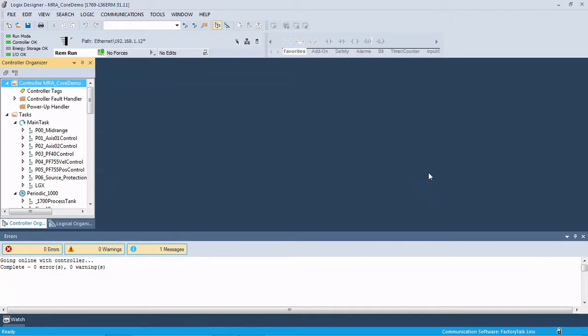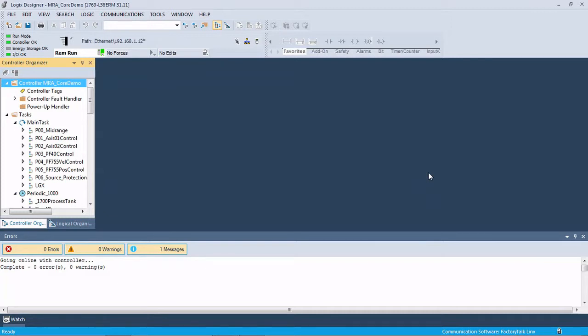So there is a way to use the SD card in the 1769 L31, L32, and L33, as well as the ControlLogix processors, the L7s and L8s. Use the SD card to backup the firmware and the code so that you can just load it into a new processor and be up and running. So we're going to step through that real quick.